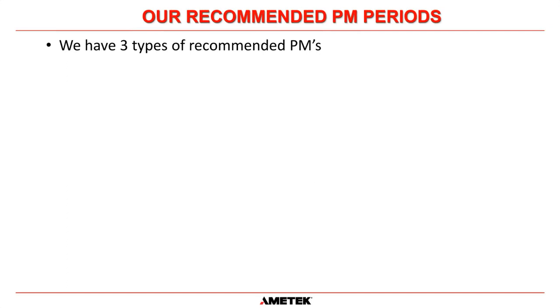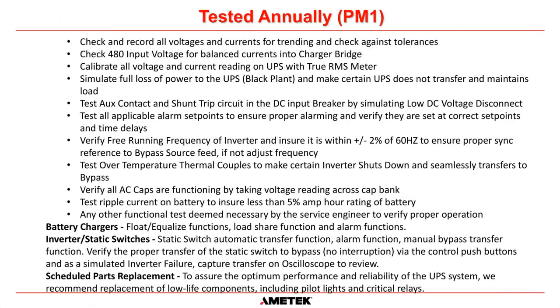And we have three types of recommended PMs within our systems. This is AMETEK SCI as a whole, okay? And I'll list them on each separate page. The first one is what we do on an annual PM, or what we call a PM1. So first of all, we check and record all the voltages and currents for trending, and we check against all the tolerances for our UPS.